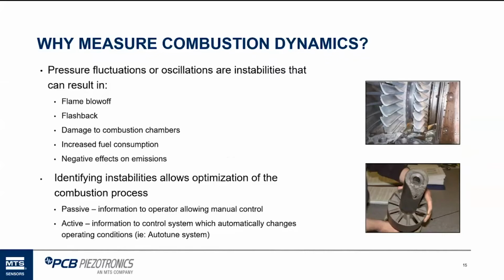If you've got the wrong fuel air mixture, you can increase your fuel usage, which can be very expensive. Natural gas is pretty expensive. That's one of the most expensive parts of operating a gas turbine power plant. And then, depending on the area where it's mounted, the emissions standards for that plant might be really strict, so they have to run within a real tight air fuel mixture to keep their emissions level at a certain standard so that they don't exceed that and get in trouble from the EPA.